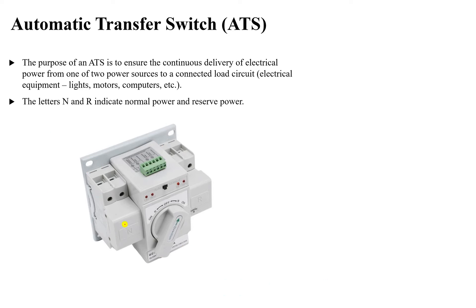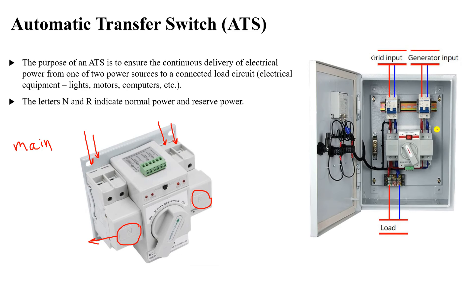As you can see in this figure, the ATS has two letters: N and R. N represents the normal power — our normal power or utility grid, for example, or an electrical generator — the main or primary source of electrical power is connected here. The reserve power or backup power is connected at R. For example, the primary source is the grid and the backup source is the generator.